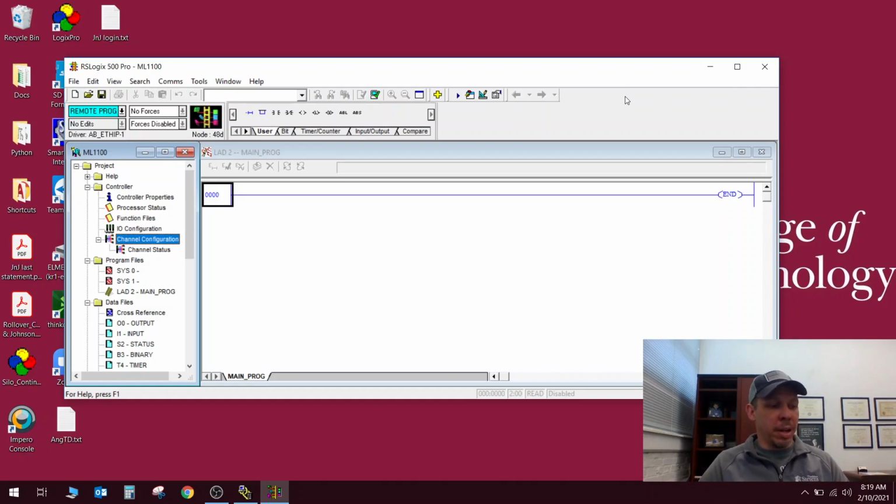And you're going to want to write it down, either in the cabinet that this processor is in, or on the side of the processor, or put a sticker on it or something, because if it's not on a network and it's a freestanding processor, you need to let everybody else know in the future what IP is set in it. These MicroLogix 1100s are nice because you can scroll through the screen on the front and find the IP address in it, but other stuff like the 1000s and other models don't display what the IP address is, you just have to know.